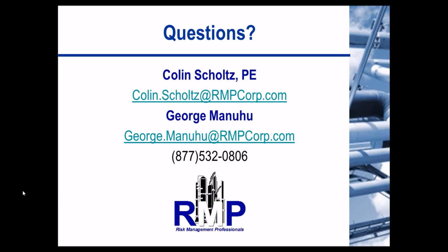All right, here's a question. PSM requires inspections and test frequencies consistent with the manufacturer's recommendations and industry best practices. Are there pieces of equipment that require more than B109? Okay, so the question is, PSM requires inspections and test frequencies consistent with manufacturers' recommendations and industry's best practices. Are there pieces of equipment that require more than B109? And so there is equipment that does require more inspections than what is required by the B109. One of these, the condensers, should be inspected more than annually, even though this isn't entirely spelled out by the manufacturers, but this is something that's learned on a facility-by-facility basis.